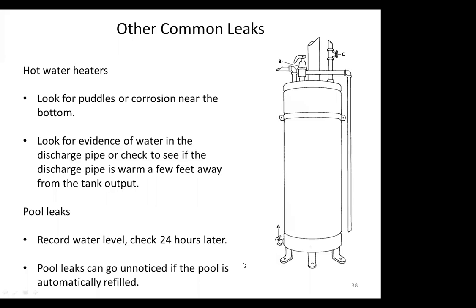Other common leaks include hot water heaters. Hot water tanks most often leak due to a faulty pressure relief valve. You can find this by looking for evidence of water in the discharge pipe, or if you can't find that, checking to see if the discharge pipe is warm a few feet away from the tank output.